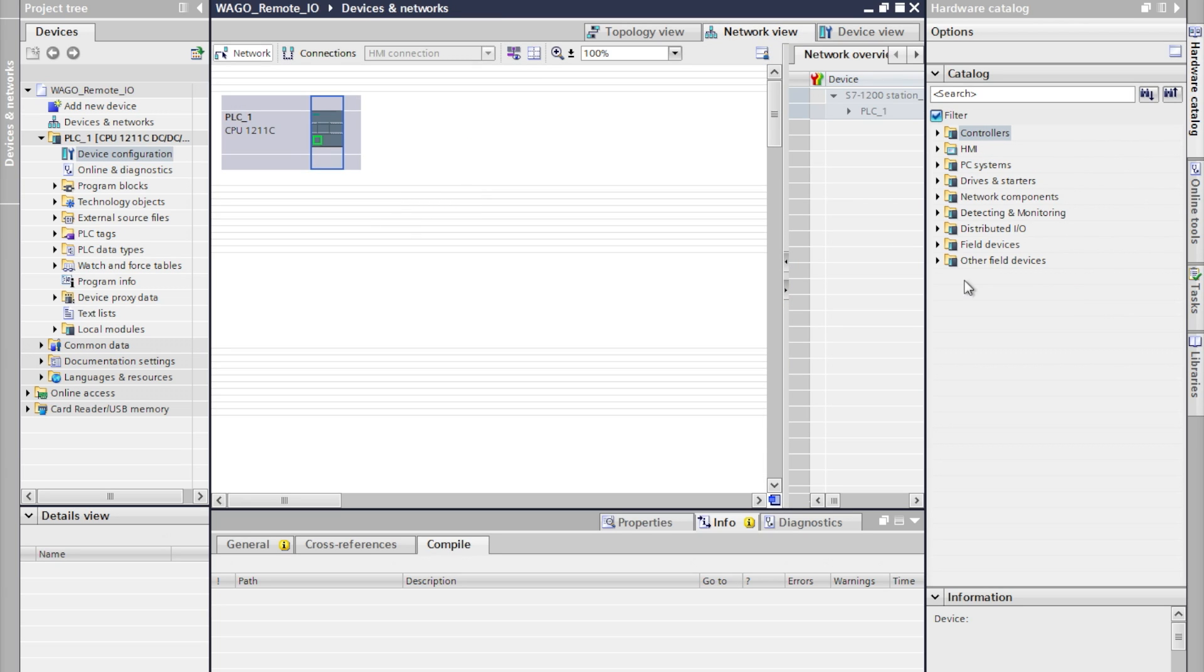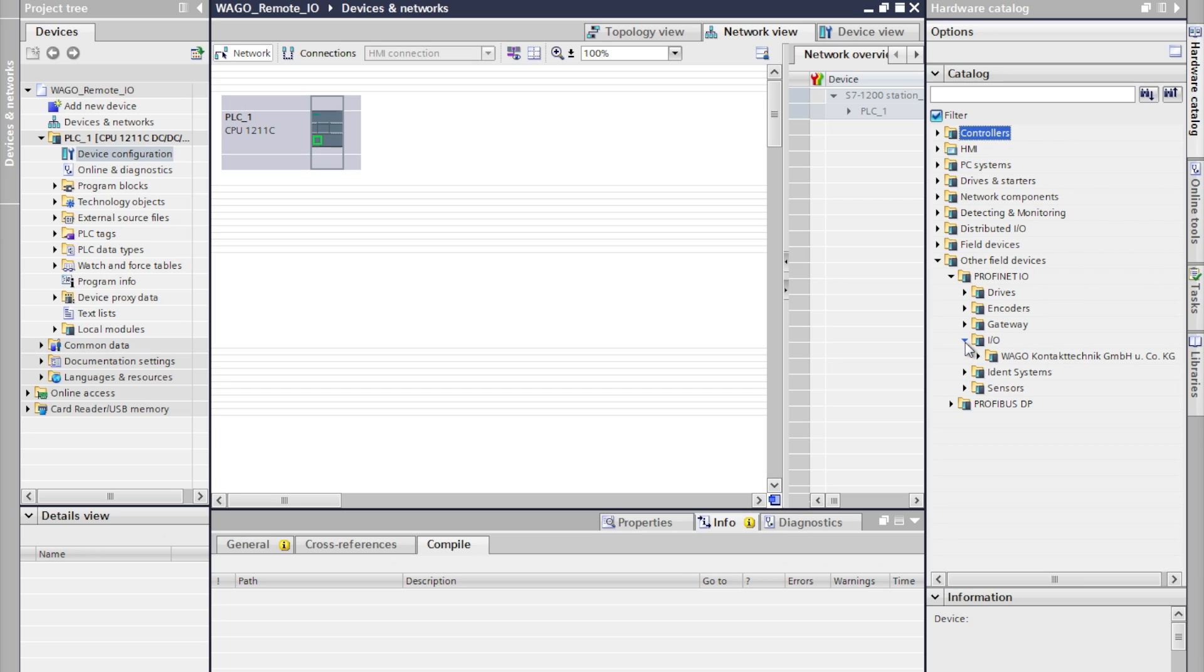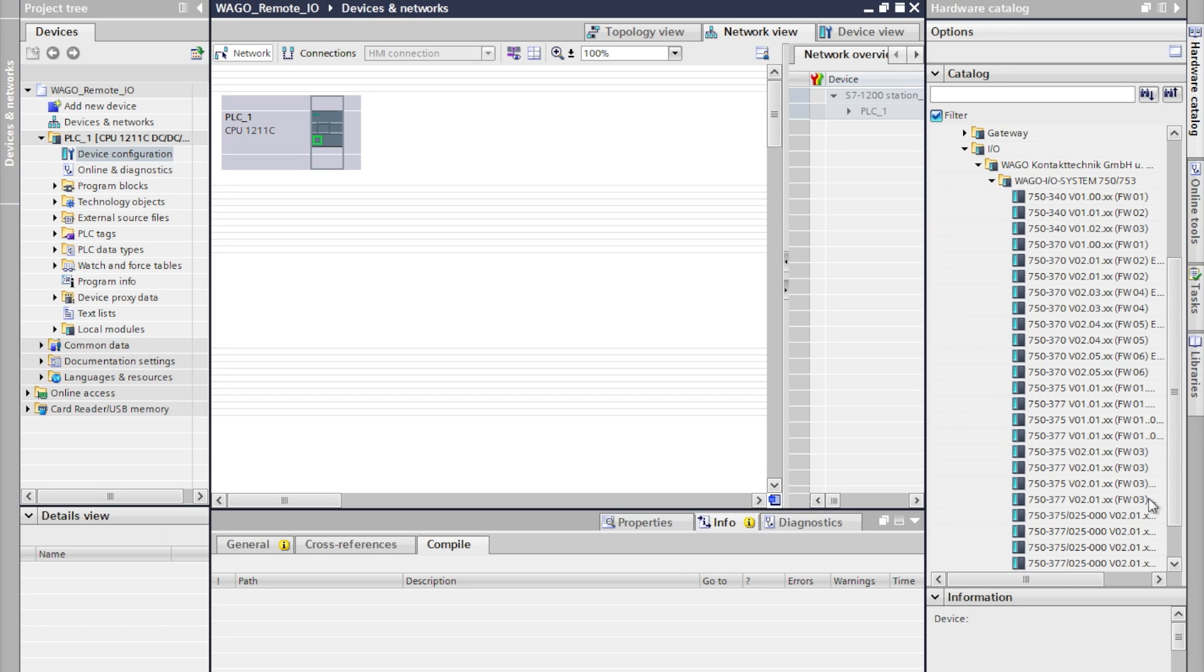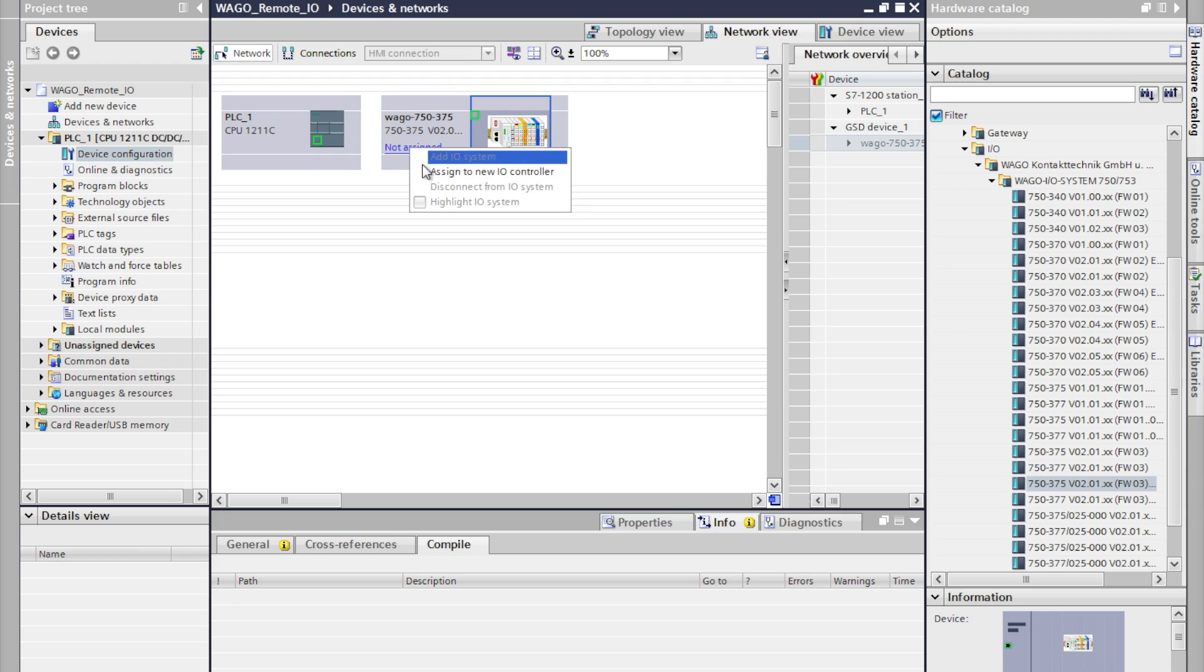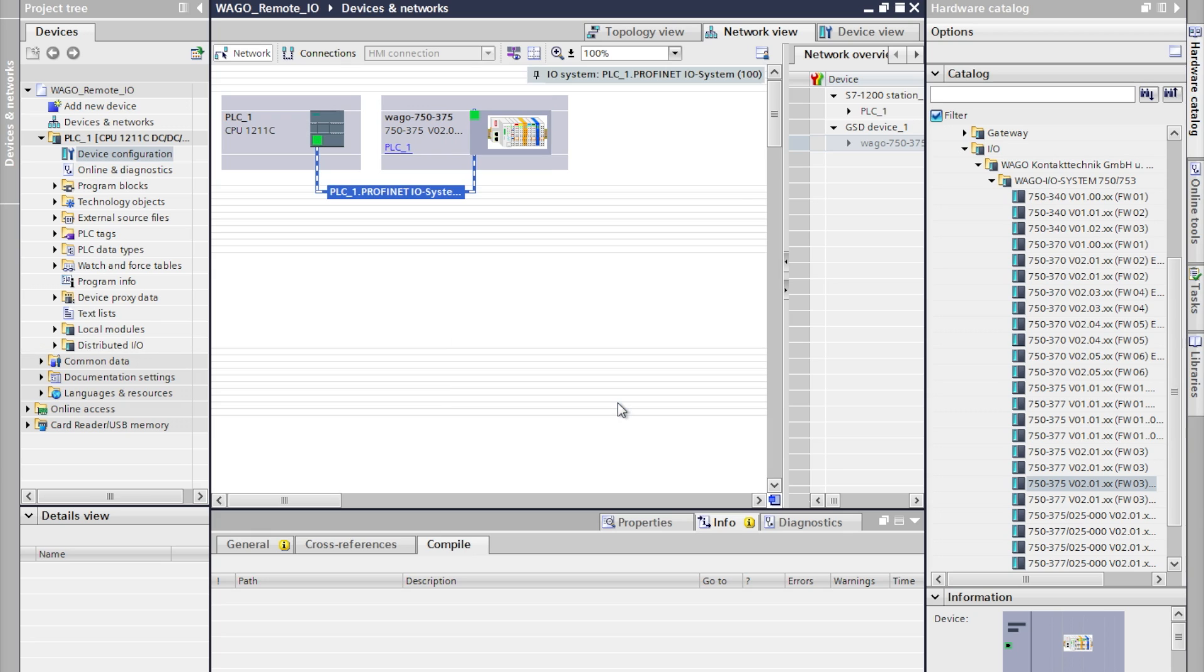We'll go into network view and now we'll use the hardware catalog on the right to select other field devices, PROFINET I/O, WAGO and expand the WAGO 750-753 menu. We'll select our coupler which is 750-375 and by double clicking add it to the I/O assignment. You'll notice that this is not assigned to a PLC so we'll right click on not assigned and assign it to the S7-1200 that we're using.